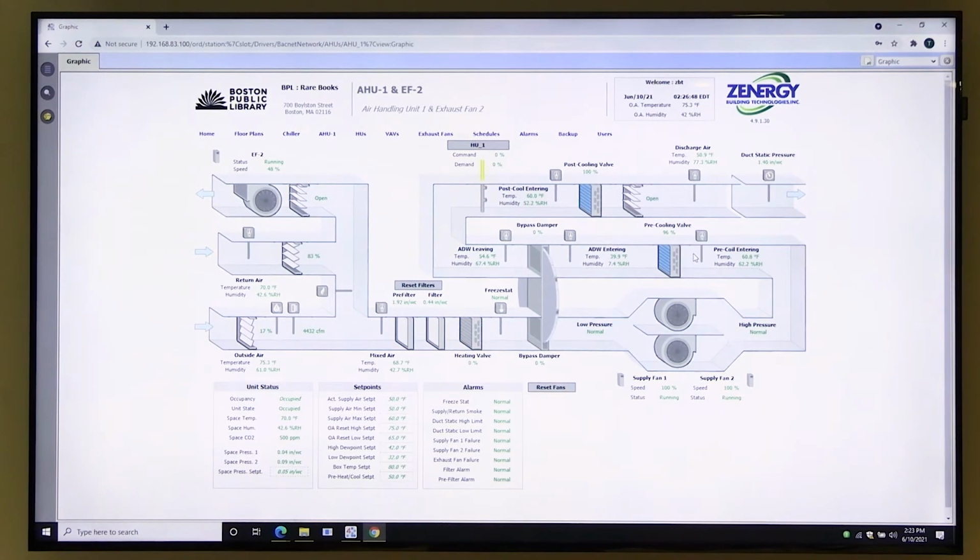We're basically trying to get that air nice and cold and get as much humidity out of there as possible. At which point it then hits the wheel and we heat it back up with the energy that came from the mixed air temperature. So it's just a process of wringing out the air and heating it back up, to dry out the air, so take some of that moisture out, in the summer where there's a lot of moisture in the air.